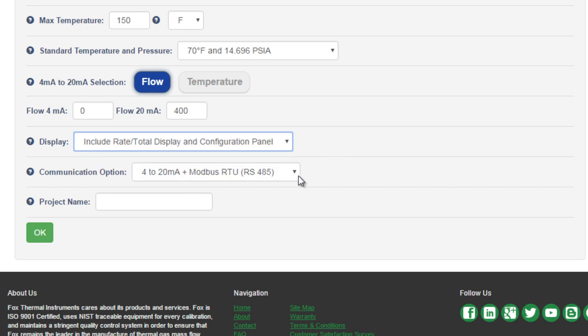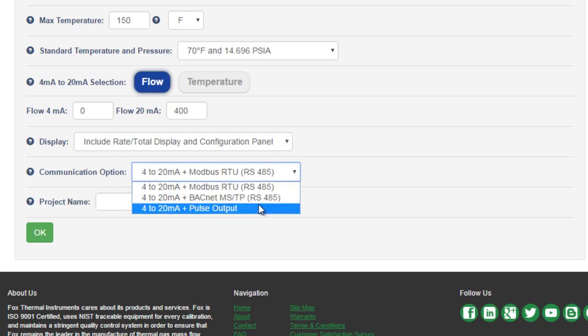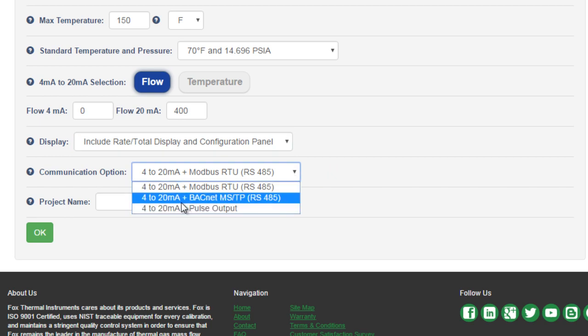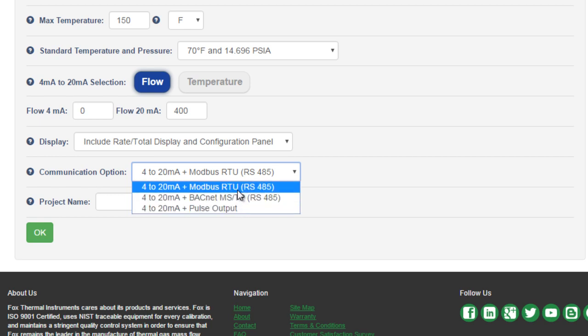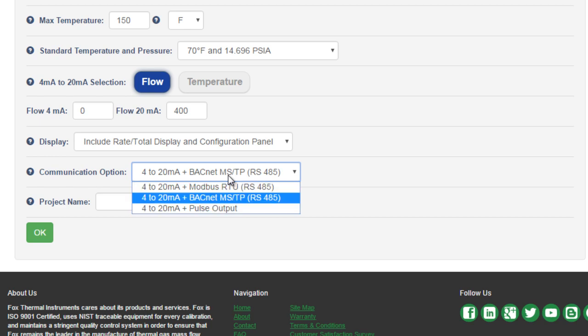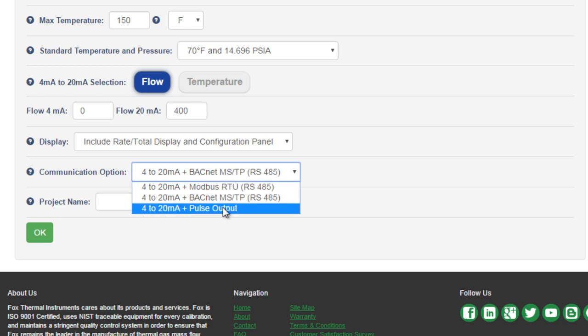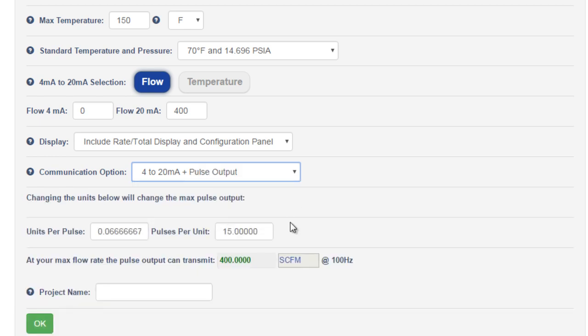Next, you'll choose your second output from the meter. The standard output is your 4 to 20 from above plus a pulse or frequency output. The other options are RS-485 outputs for BACnet or Modbus. If we choose Modbus or BACnet, that's all we need to do for this step. If we choose the pulse output, you can configure the units per pulse or pulses per unit settings on the meter. These values default for your application's maximum flow rate at 100Hz.